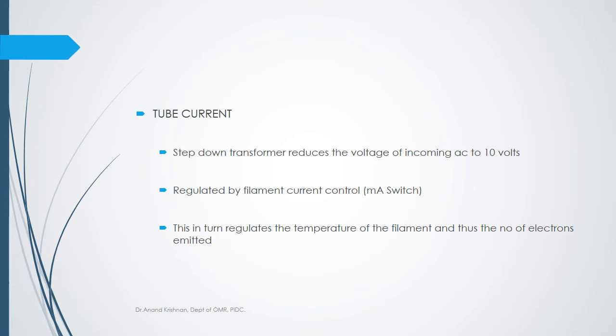So the mA, the amount of current that you are passing through the filament, is directly proportional to the number of electrons emitted.